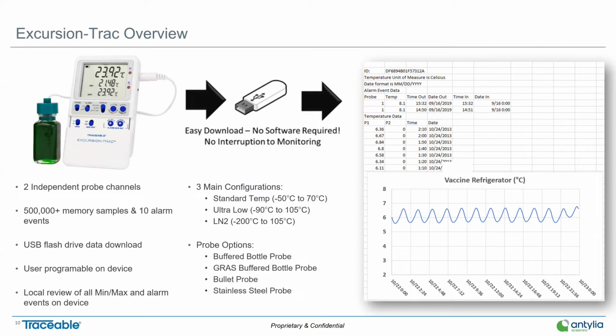The device does allow a local review of the mins and maxes that the device has experienced since its last clear. And like I said, you can view the last 10 alarm events on the device screen itself with their timestamps. So if you're just doing a quick audit, you see that something's gone off, you can go in and look really quickly and understand what that alarm event was and make a decision as to whether or not you need to download the data to understand more about what's been going on with the samples or products that Excursion-Trac is monitoring.